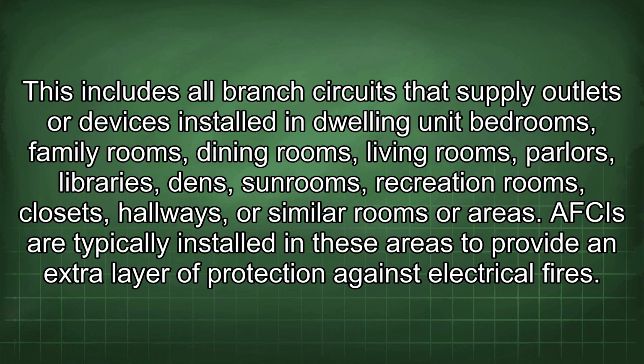This includes all branch circuits that supply outlets or devices installed in dwelling unit bedrooms, family rooms, dining rooms, living rooms, parlors, libraries, dens, sunrooms, recreation rooms, closets, hallways, or similar rooms or areas. AFCIs are typically installed in these areas to provide an extra layer of protection against electrical fires.